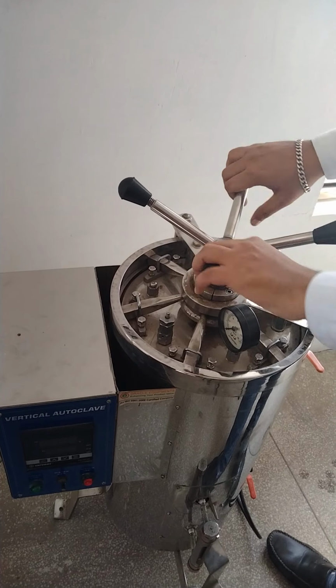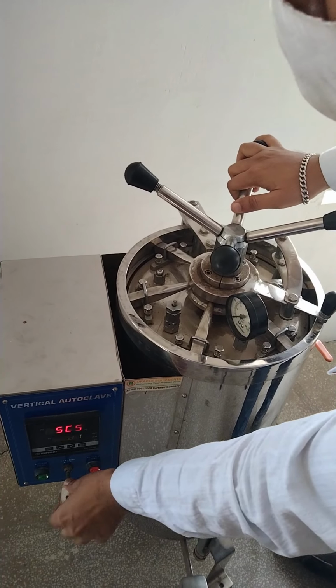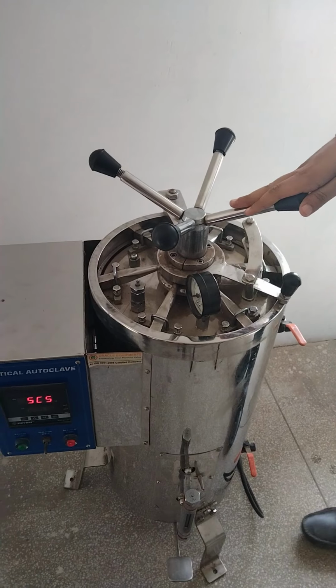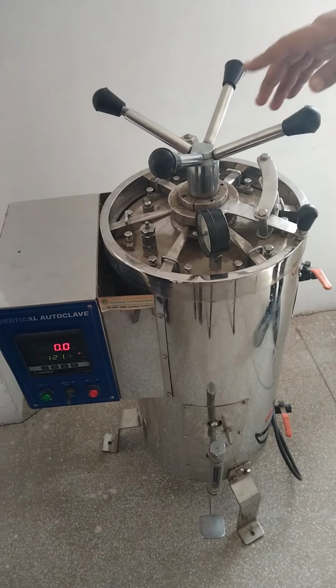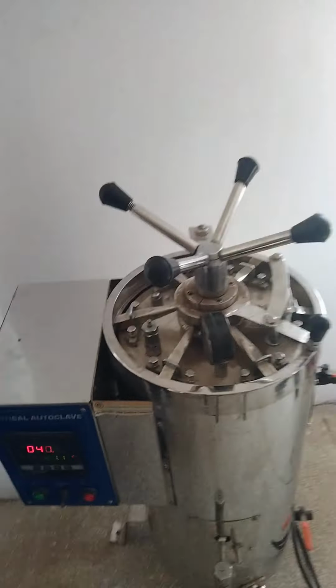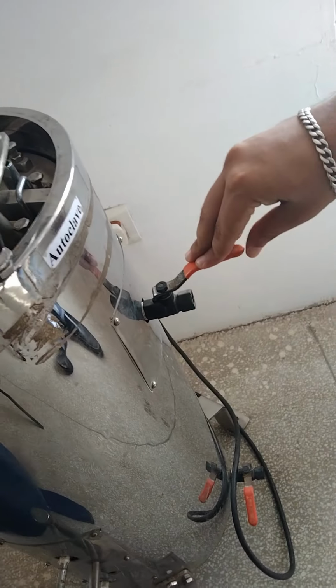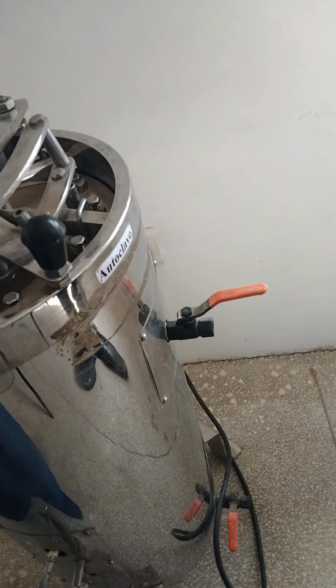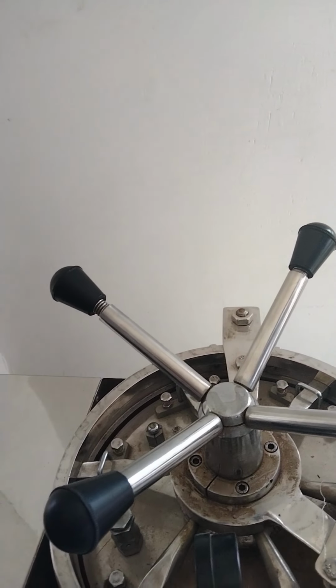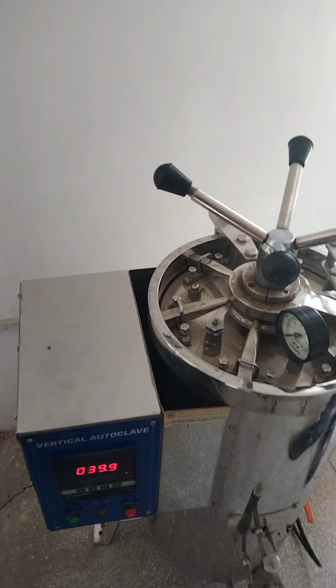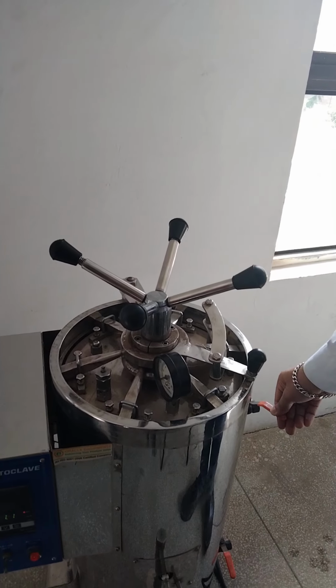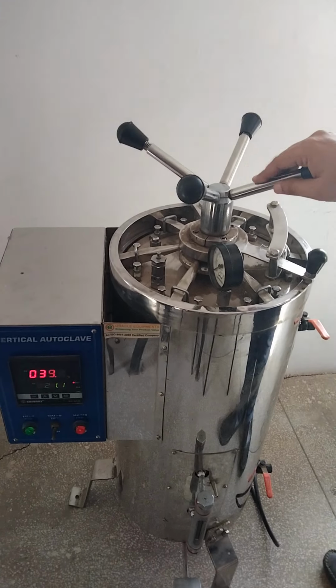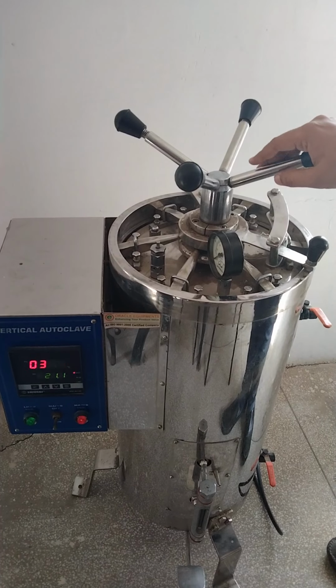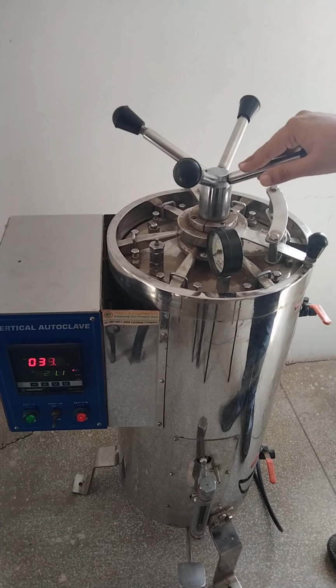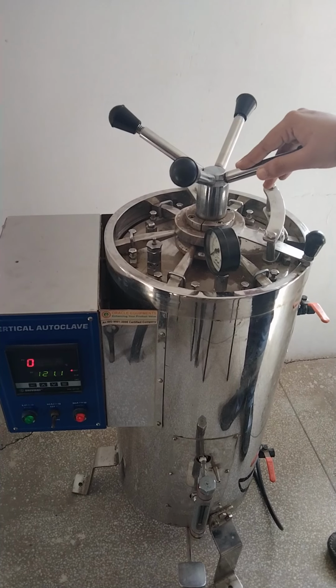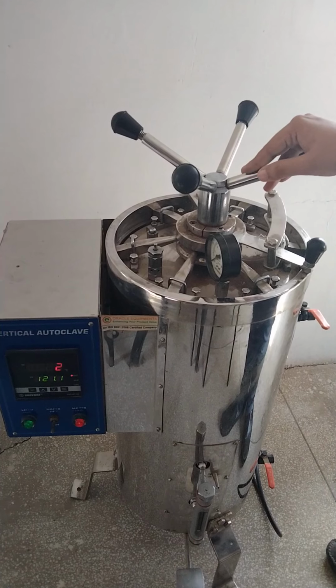Then you have to switch on the main switch, and it will start heating. Then you have to allow the steam to escape for some time through the side safety valve so that the air is removed, so the whole chamber is filled with steam only. After heating, the pressure should reach 15 psi and the temperature should be 121 degrees Celsius, and you have to heat for 20 minutes. After that, you have to stop the heating and allow it to cool, and after that you have to open the lid and remove the sterilized material.